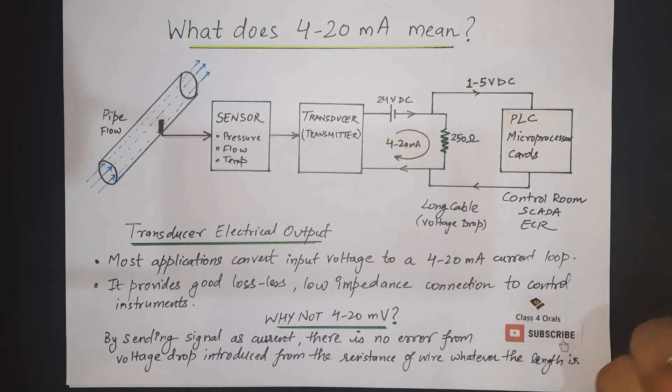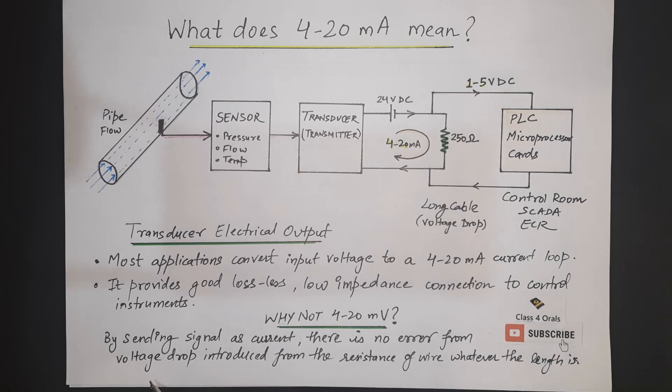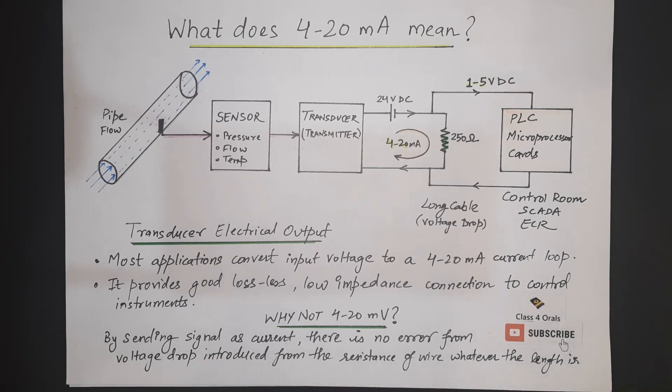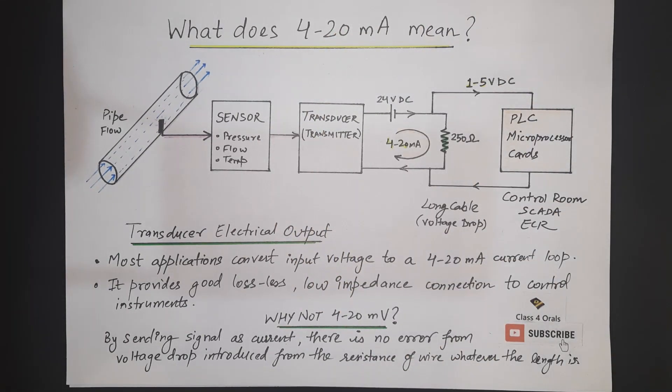This is why we are focusing to measure the signal in the form of current and not in the form of voltage because the voltage drop introduced from the resistance of the wire whatever the length is there will be some error that is why we do not want that error to come hence we are sending the signal in the form of 4 to 20 mA and not 4 to 20 mV.